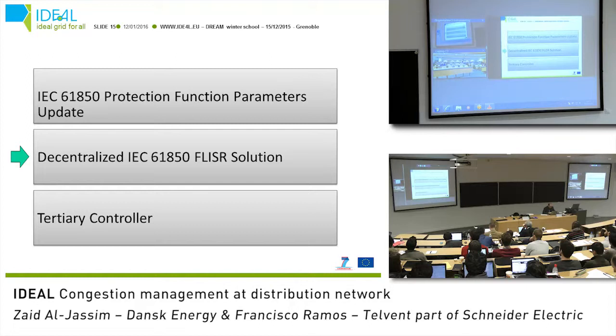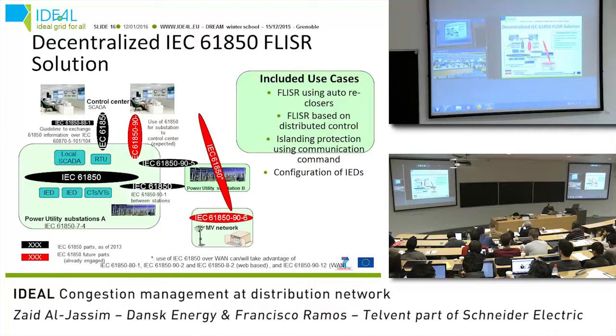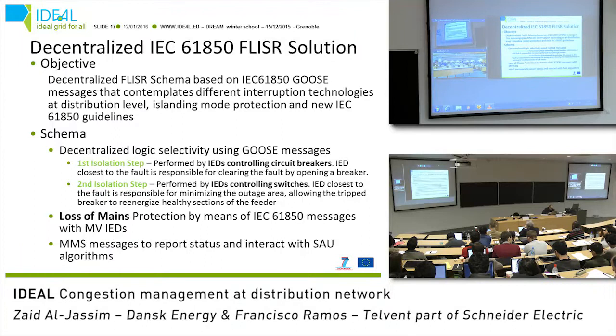The second important activity, and the main one, is the decentralized FLISR solution itself. In this slide, you can see the part of the standard that we are working in for the feeder automation solution, which includes some interesting use cases for us, like FLISR using auto recloser and FLISR based on distributed control. Of course, there are also parts for islanding, etc., and configuration of IEDs. In this activity, our main target was a decentralized FLISR solution using GOOSE messages and taking into account the standard.